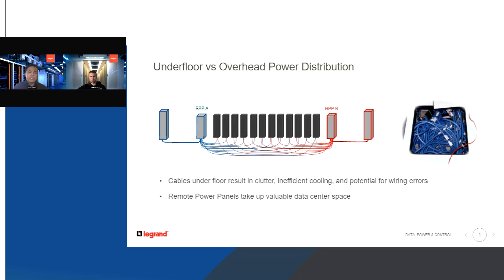To start, I wanted to show you what kind of predated Busway before it became more of a mainstay in the data center space. What you're seeing on the screen is an RPP setup from an A-B. The way it was done previously is through a raised floor: you would route, in a typical scenario, an RPP output of a breaker down through that raised floor and then up to where it's intended to power the rack. Using that raised floor with cables really resulted in clutter, inefficient cooling, and a potential for wiring error since you're less visible to where you're routing wires from and to. So we were really seeing this take up a lot of valuable data center space.